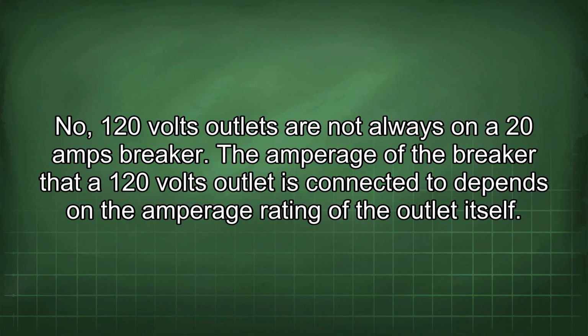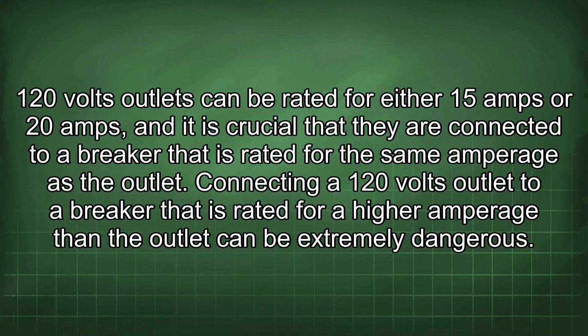No, 120 volt outlets are not always on a 20 amp breaker. The amperage of the breaker that a 120 volt outlet is connected to depends on the amperage rating of the outlet itself. 120 volt outlets can be rated for either 15 amps or 20 amps, and it is crucial that they are connected to a breaker that is rated for the same amperage as the outlet.